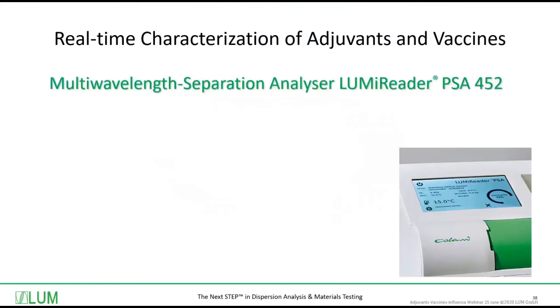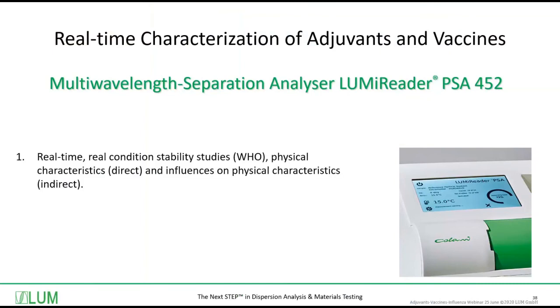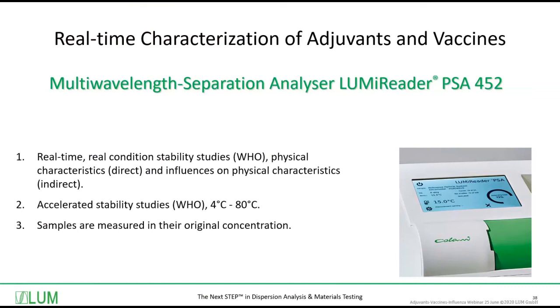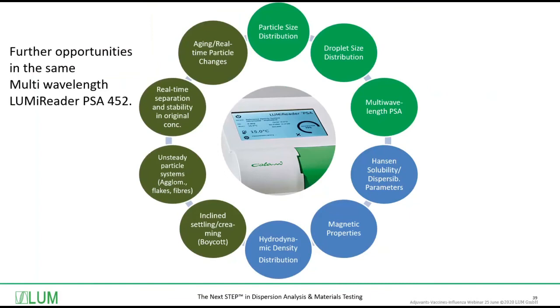Let me now summarize the presentation. When we talk about real-time characterization of adjuvants and vaccines, we refer to the multi-wavelength separation analyzer LumiReader PSA, now in the most modern version, PSA 452. We can perform real-time, real-condition stability studies according to WHO with a focus on physical characteristics directly, and indirectly characterize other characteristics if they influence physical behavior. We can also perform accelerated studies according to WHO because the instrument has a temperature range from +4°C up to +80°C. All samples are measured at their original concentration.